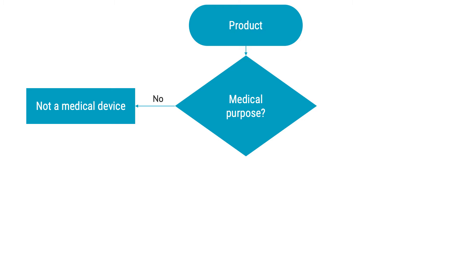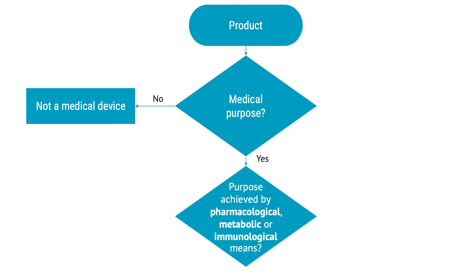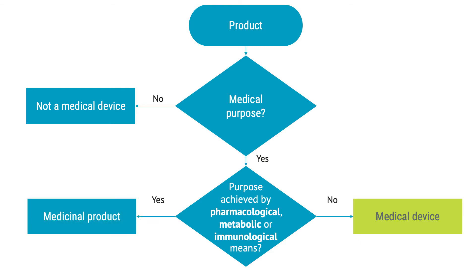But there is one more thing you need to consider before getting to that conclusion. You have to define how your product achieves its primary purpose. And this is what makes the difference between whether your product is a medical device or a medicinal product or pharmaceutical. If the purpose is not achieved by pharmacological, metabolic or immunological means, the product is likely to be a medical device. On the contrary, if the primary mode of action is pharmacological, metabolic or immunological, the device is likely to be a medicinal product.